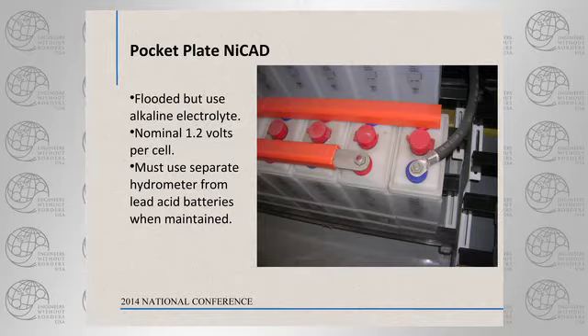The battery electrolyte is bad news in your face. You'll tell these batteries apart from a lead acid battery because the label will probably say NiCad, and NiCad products are always a nominal 1.2 volts per cell. So if you're reading a battery and can see from the molding how many cells are in it, and you notice it's only about 1.2 volts a cell, that means it's a NiCad battery with an alkaline electrolyte rather than an acid electrolyte.